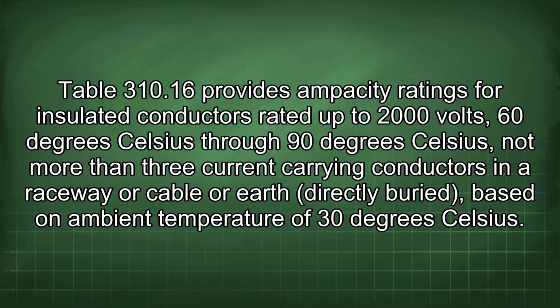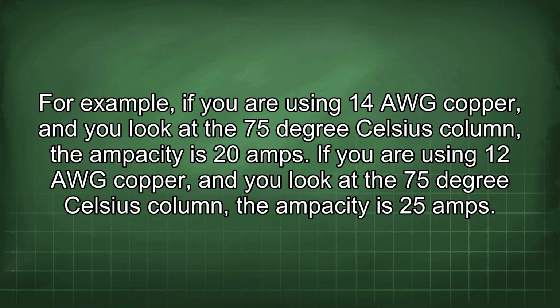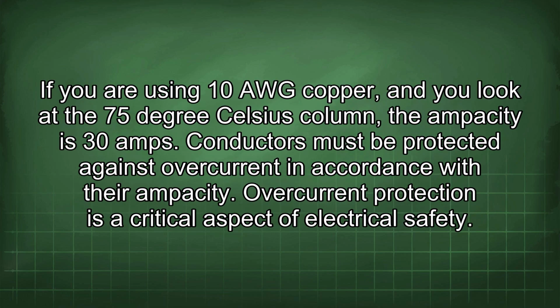30 degrees Celsius. For example, if you are using 14 AWG copper, and you look at the 75 degrees Celsius column, the ampacity is 20 amps. If you are using 12 AWG copper, and you look at the 75 degrees Celsius column, the ampacity is 25 amps. If you are using 10 AWG copper, and you look at the 75 degrees Celsius column, the ampacity is 30 amps. Conductors must be protected against overcurrent in accordance with their ampacity.